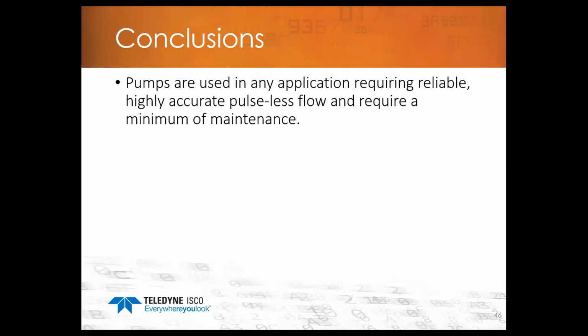The main advantage of a syringe pump, of course, is the accurate pulseless flow. And really, as far as maintenance is concerned, our syringe pumps are pretty low maintenance. Basically, just regular lubrication and changing the seals. There's really no time frame as far as the seals are concerned. If you want to get into a regular maintenance schedule, that'd be fine. Most users don't change the seals until they leak.